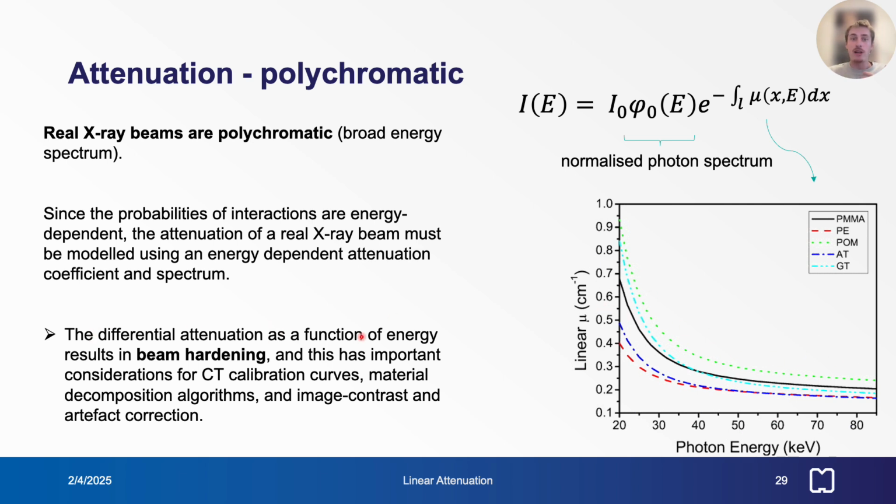Now, the differential attenuation as a function of energy, as we know, results in beam hardening. And this has really important considerations for CT calibration curves, material decomposition algorithms, and image contrast and artifact correction.